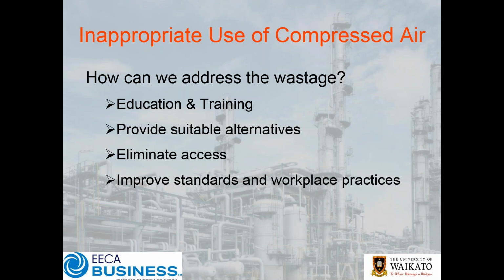I'm aware of a site just this year actually that eliminated compressed air being used where it didn't need to be. They didn't even need to replace it. They actually had an improvement in quality, and they reduced their air use by over 30% at no capital cost. Just by asking the right questions and proving that it was a viable alternative, not only did they reduce their power consumption, they actually had an improvement in quality.